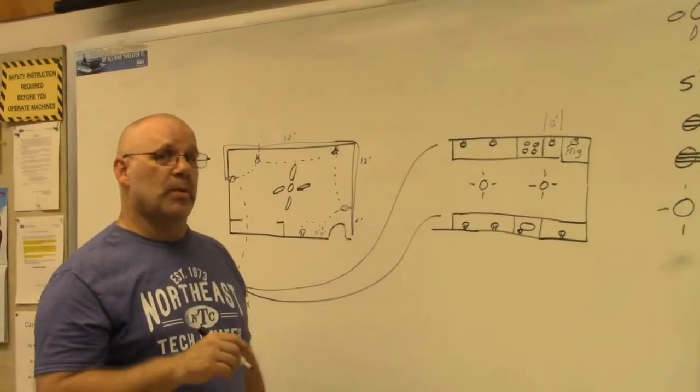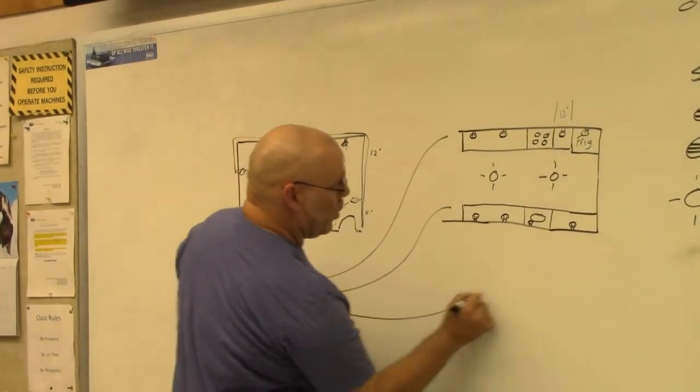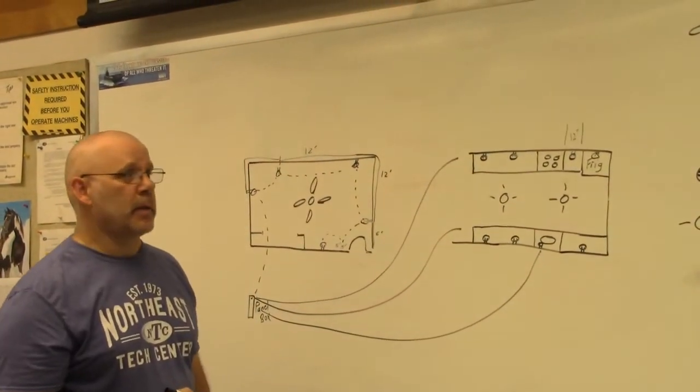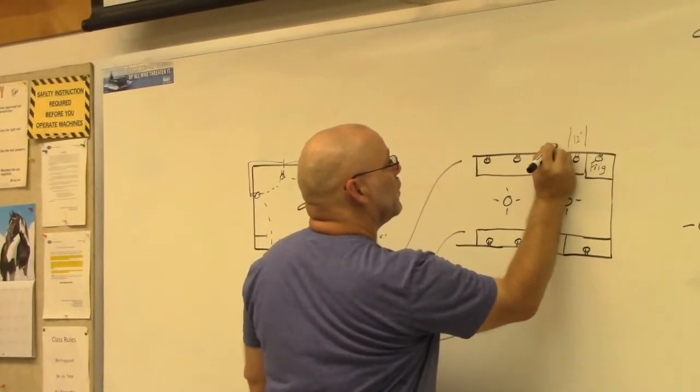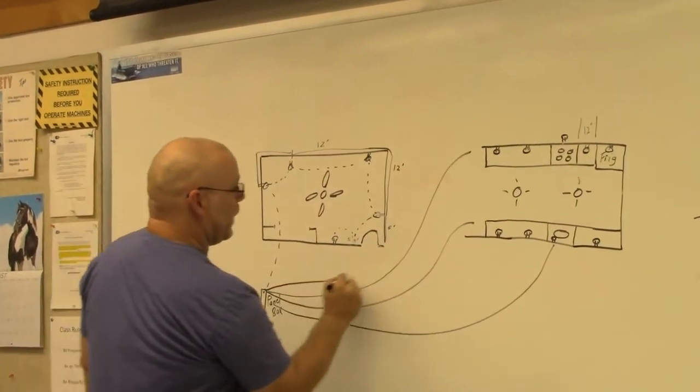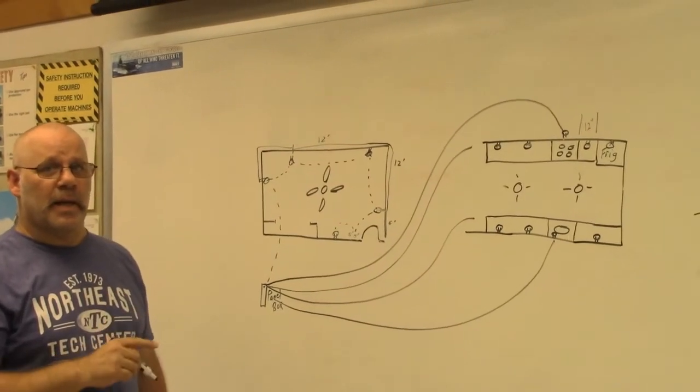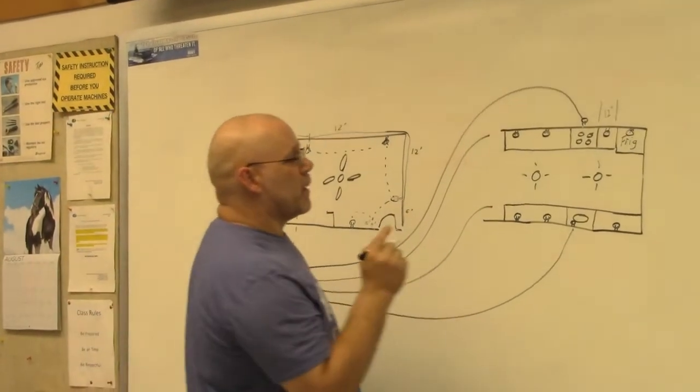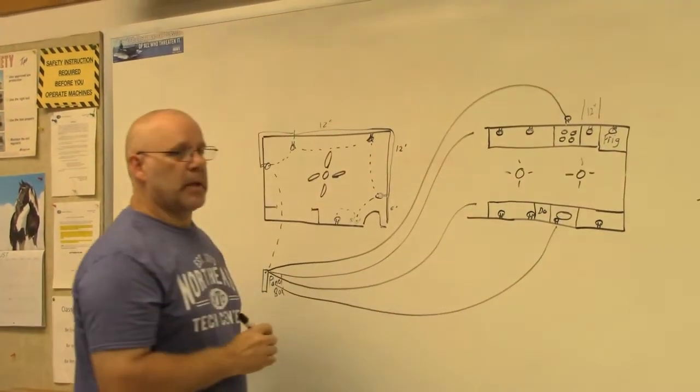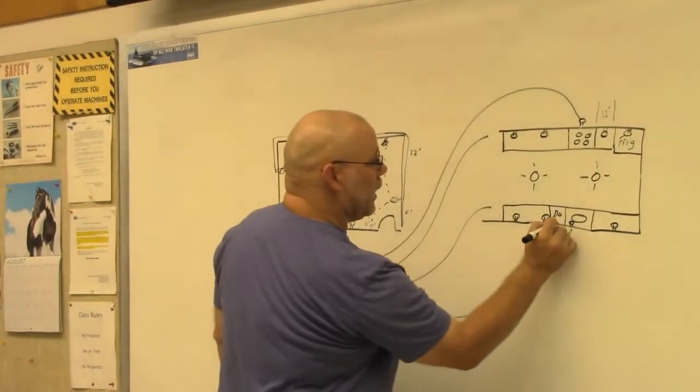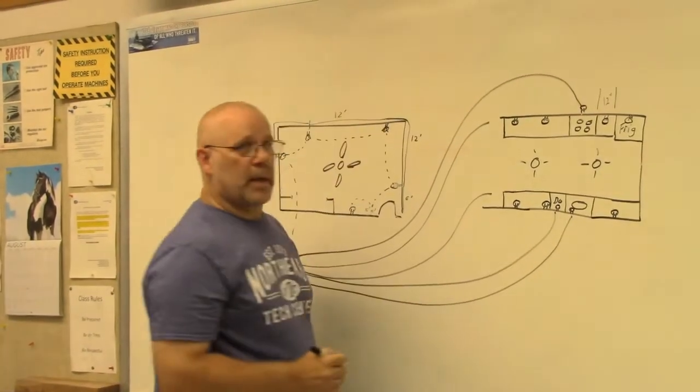But a disposal is a dedicated circuit, which means it has to have its own home run. If I have a microwave above my stove, it has to have its own home run. That is a dedicated circuit. If, let's say I have a dishwasher next to my sink, it would get an outlet with a dedicated circuit.